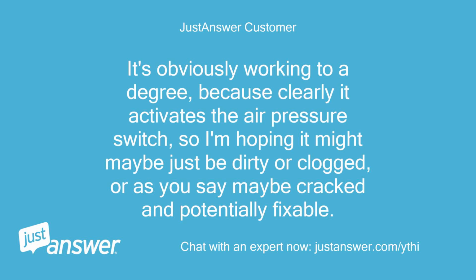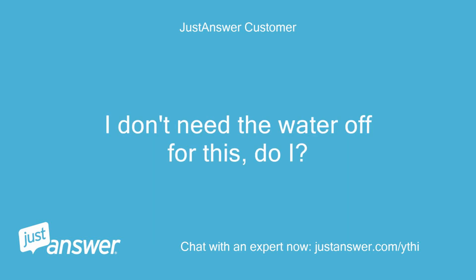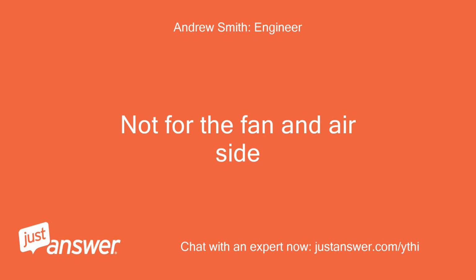It's obviously working to a degree, because clearly it activates the air pressure switch. So I'm hoping it might maybe just be dirty or clogged, or as you say maybe cracked and potentially fixable. I don't need the water off for this, do I? Not for the fan and air side.